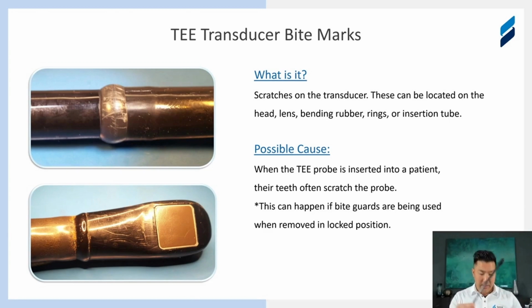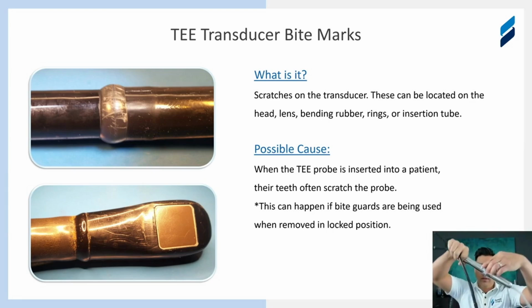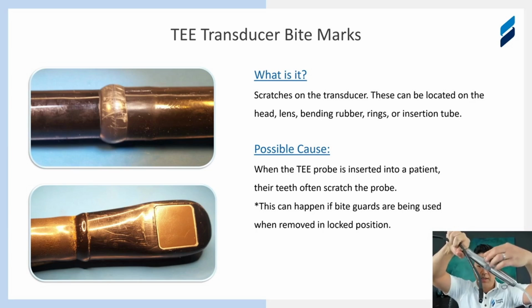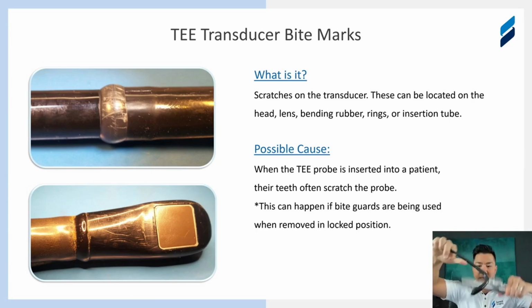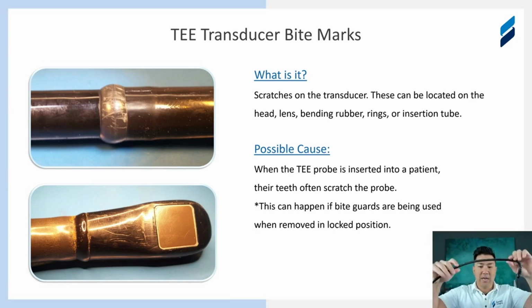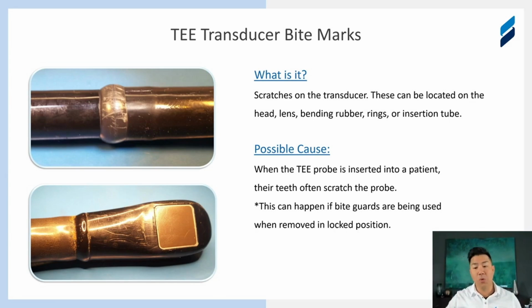What we often see is that these probes have locking mechanisms here. You can actually rotate this probe all the way forward and lock it, and you can see now it's in a lock position. So imagine this is actually inside a patient getting a wonderful scan of the heart, but when the procedure is done, this isn't unlocked, and now it's in a forced position to come out and drag against the back of the molars, causing those kinds of deep scratches. We highly recommend you release the probe, get it straight, and then pull it out, and that will prevent a lot of this deep bite mark and scuffing damage. Where it becomes really an issue is if we look at the lens here.